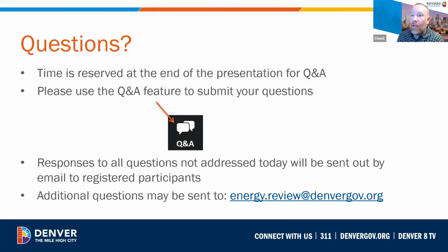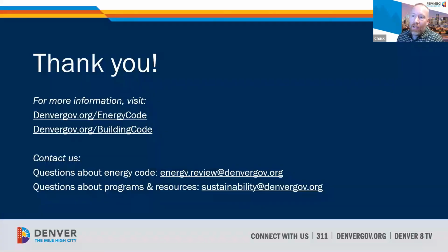C403.2.4 will not allow the gas backup for the heat pump. You are allowed to use the electric resistance as a backup. The exception to that is if you are replacing a fossil fuel furnace, you're allowed to install a heat pump with a gas backup. So if you're replacing an existing gas-fired piece of equipment, then yes, you are. But if it's a new system in a building, not replacing an existing gas-fired piece of equipment, then no, you are not able to.